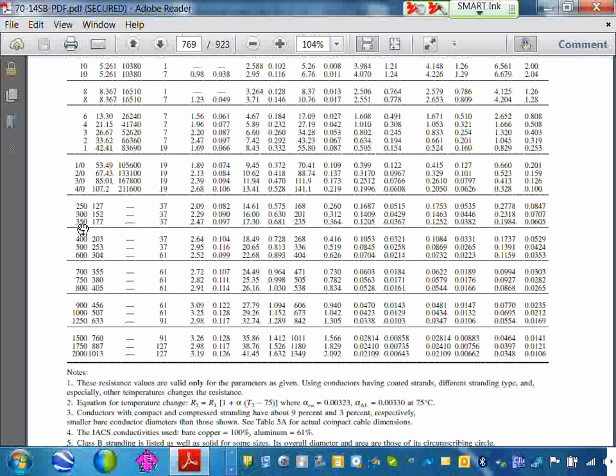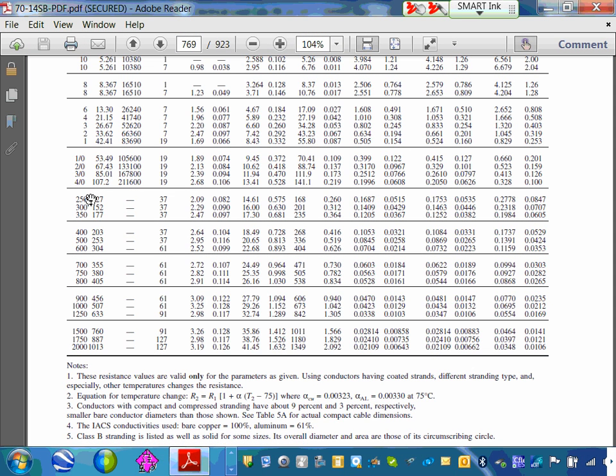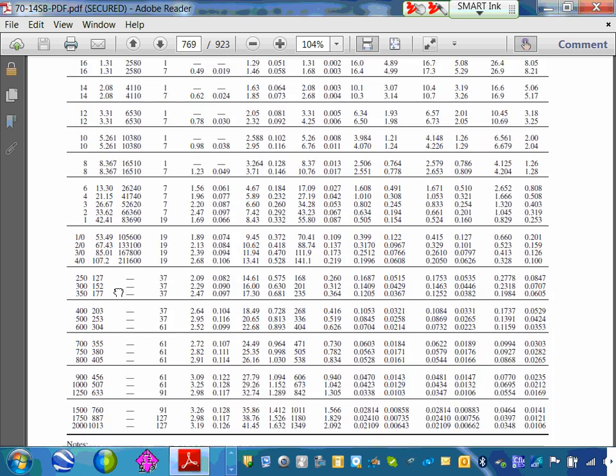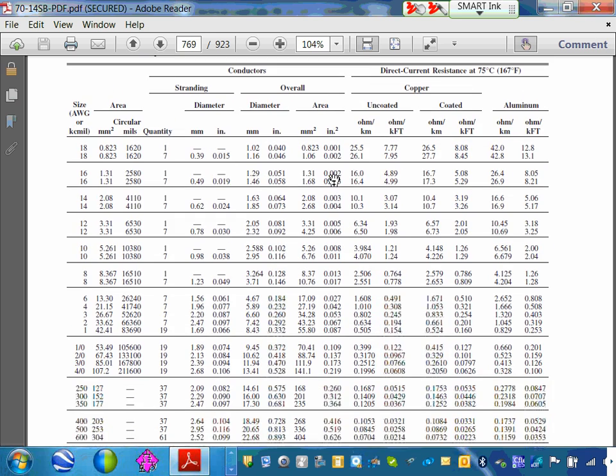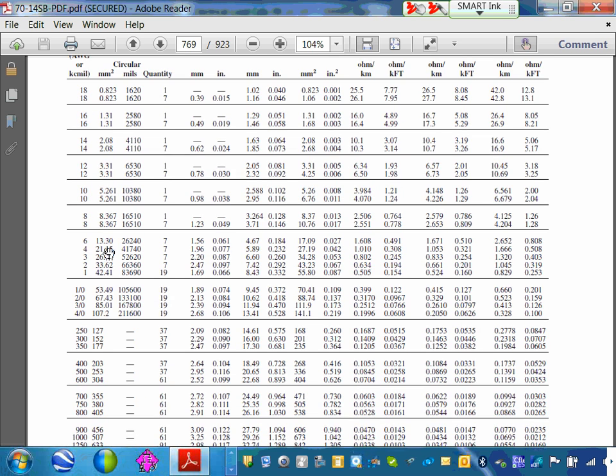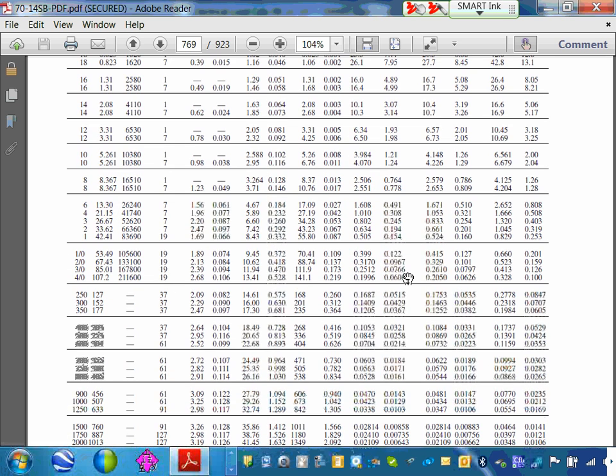Unless you're willing, like Chad, a registered engineer, to drop the one and sign off on 300, which you can. As an engineer, you can. But for cover-your-butt type design, you always go to the next standard. Okay, so that's how we use this table, guys. So please highlight it. These are all the sizes. Obviously, we use this table for other things that we're not going to talk about at this time. It will also give you the circular mil. So what happens if you came up, guys, with a circular mil of, let me just pick one, we did math, and you came up with a circular mil of 100 KCM? Do they make 100 KCM? 250.